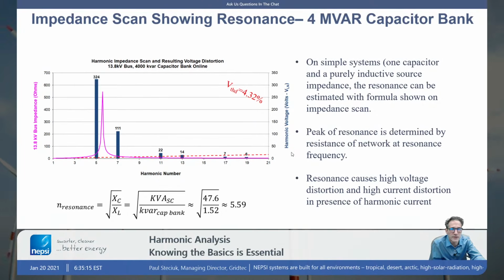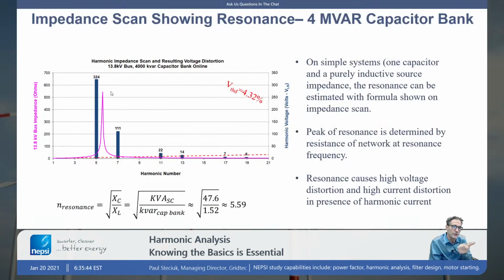Okay, so the next thing to talk about here is that if we were looking at this, we might say that this system is okay. We don't have a 5th resonance. I don't have a 7th resonance. My voltage distortion is at 4.32%. But I look at the impedance curve, and the first thing I know is, well, what if it were to shift to the left? What if it were to shift to the left? I don't have any harmonic current right now at the resonant point here. I'm slightly off to the left. My resonance is slightly to the right of me.